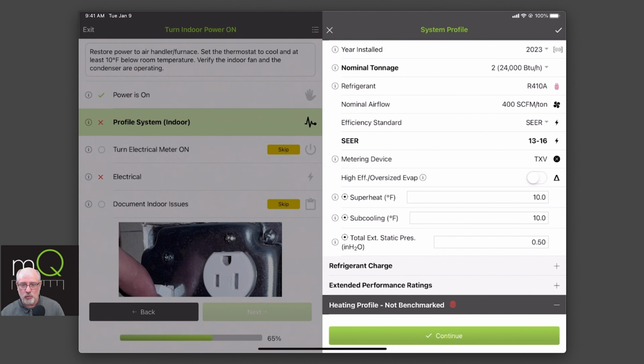Static is now a new world. Probably since I was born it's been 0.5 inches, right? And now we have Bosch systems and others that are 0.8. If your profile is actually 0.5 and you're reading a Bosch system at 0.8, it's going to be a fault. We're going to tell you that your static pressure is excessively high and deduct almost 20 points for an improper static pressure, when it was actually correct. It was your profile that had failed.